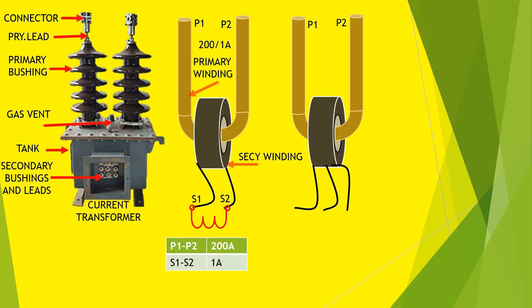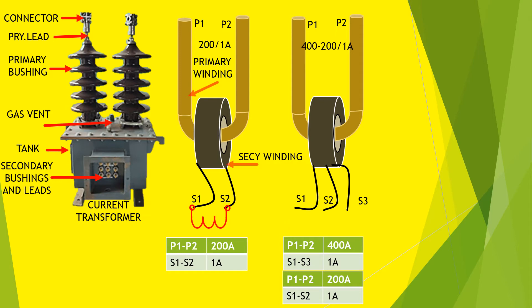Here the rating is 400/200 by 1 ampere. That means the magnitude of normal current along P1 and P2 is either 400 ampere or 200 ampere, and depends on shorting either of S1 and S3, or of S1 and S2. If shorting is done between S1 and S3, then 400 ampere normal current will be allowed along P1 and P2. If shorting is done between S1 and S2, then 200 ampere normal current will be allowed.